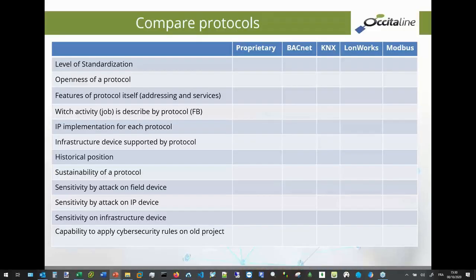Some French or international customers and clients. It's not only large manufacturers, but also a large integrator in France and many other customers. The first question we can ask is: is it very important to use an interoperable protocol? And if I want to invest or to have security in my BMS, is a proprietary solution better than an interoperable one? In fact, we try to compare a proprietary protocol, BACnet, KNX, LonWorks, Modbus, from different points of view.